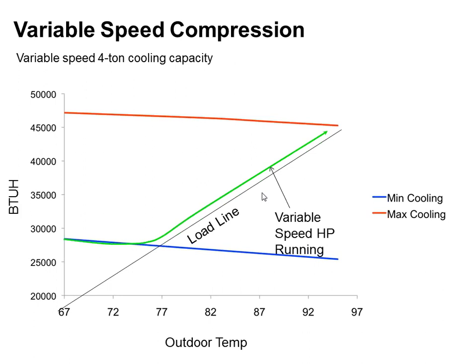One is if you walk up to the thermostat and you change the set point. Let's say you asked for 72 degrees. Now you walk up to the thermostat in the summertime and you jack it from 72 up to 75. Well, this unit is going to ramp down to minimum capacity, 40%, and then it's going to say, wow, you want 75 and it's still 72 point something in here. I better go ahead and shut off for a little while. Right? So if you change the set point, it might shut off. If your time clock changes the set point, like for nighttime setback or daytime setback, it'll do the same thing. If you go to work and it automatically goes back to 80 degrees when you're not there, it'll end up cycling off for a while.